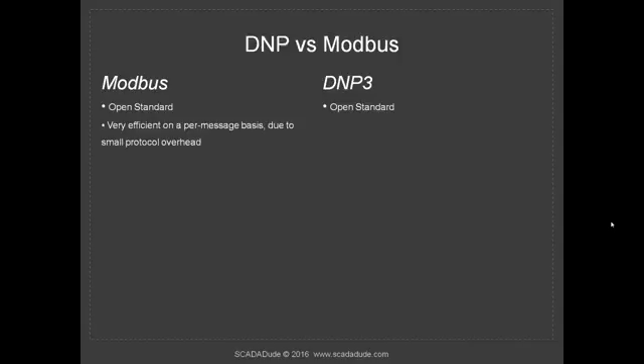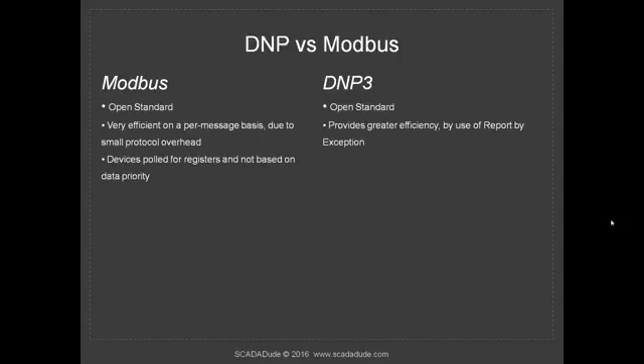Modbus is very efficient on a per-message basis because overall it's got a small overhead to it. DNP3 on the other hand is supposed to be even more efficient. The packet is a little bigger, but since it uses the concept of report-by-exception built-in, it's easier for it to do that.